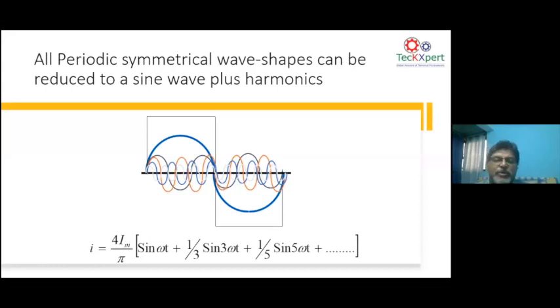Now, to explain a distorted current, the best way is to look at a square wave. If you have a square wave, by Fourier transformation we can split the square wave into multiples of the fundamental frequency. Let's say this square wave has a 50 cycle frequency. Based on the 50 cycle, you can have one fundamental sine wave, and you can have multiples of the fundamental sine wave.